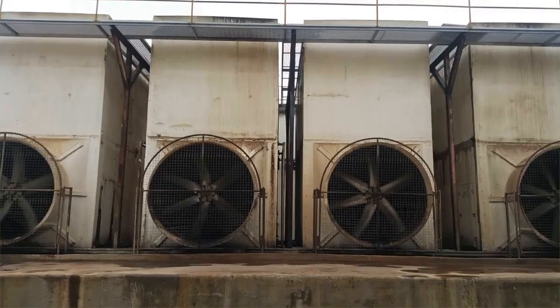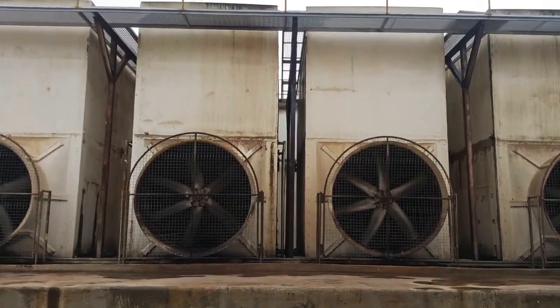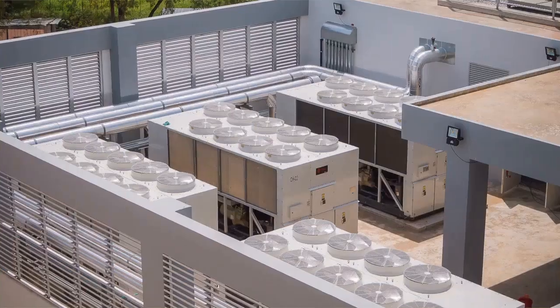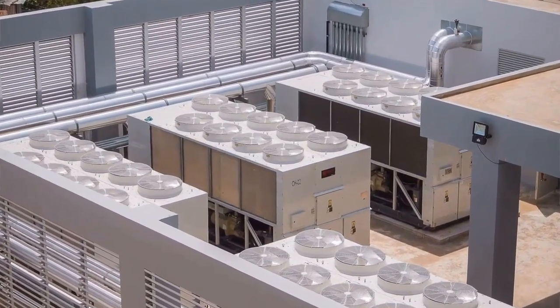In practice, when is free cooling applied? Very often, there are manufacturing industries that need to cool their processes with rather low cooling water temperatures - we're talking about 10, 15, 20 degrees. These are conditions that an evaporative tower clearly cannot meet, especially during the hot season, and neither can a radiator system.